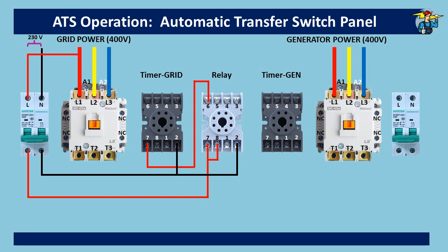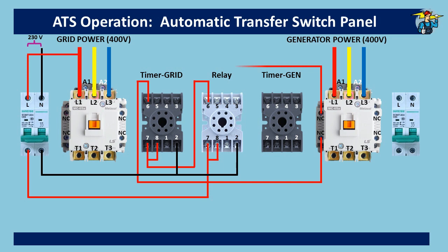On the grid timer, port 7 is connected to common port 8. After the set time delay, outlet port 6 gets power. Port 6 of the grid timer is then connected to the grid contactor operating coil A1 — on the way, it goes through the normally closed port of the generator contactor auxiliary contact, as interlocking of the two contactors is required as a safety precaution. Neutral wire is connected to A2 of the grid contactor to complete the grid side control circuit wiring.